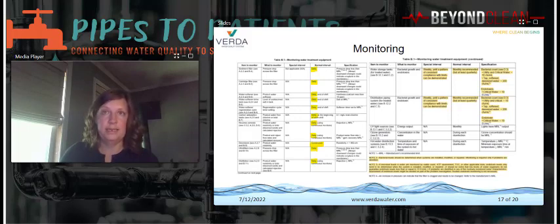For example, Table B1 lists monitoring RO product water daily for resistivity or total dissolved solids using a continuous monitor. This is best provided using an inline resistivity meter that can be checked daily or that can provide the measurements electronically. There are also daily checks on total chlorine and water hardness. Again, the documentation is important to verify all monitoring for audit purposes, as well as predictive measures to alert staff to problems as they arise. It's crucial to maintain and organize all these documents to demonstrate compliance with AAMI TIR 34 and upcoming ST 108.